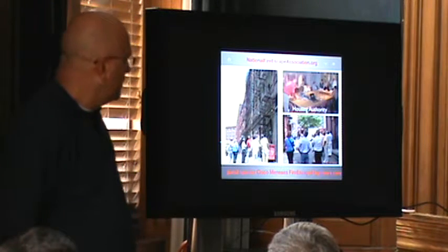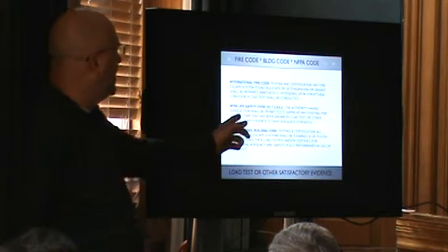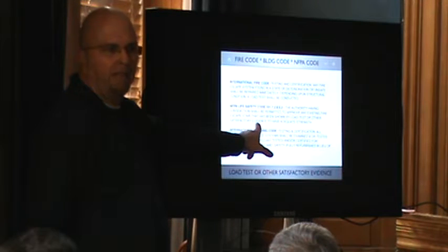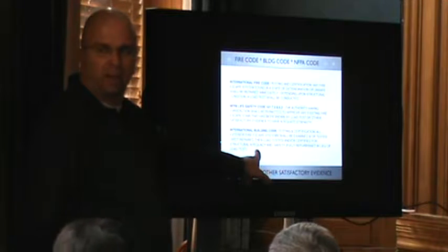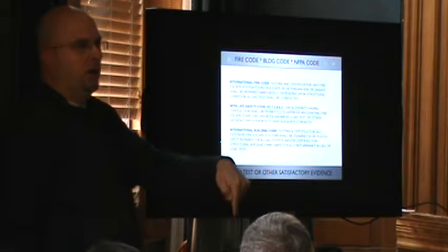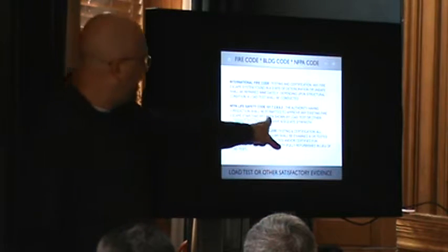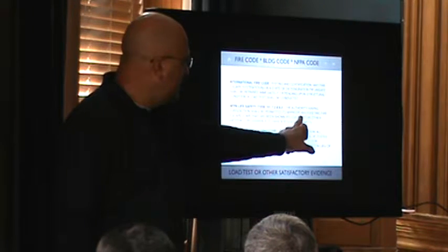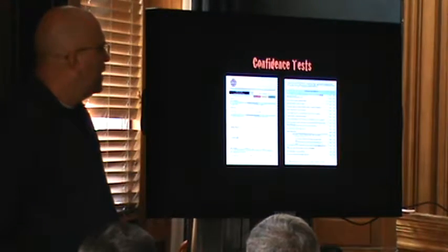Fire prevention training as well. So again, all these codes. The one thing that really helped us out was when we finally got to train everybody, we started realizing that everybody had a base of fire code, NFPA or International Building Code, and they all said the same thing. We just explained it in these classes: everybody involved in keeping a building safe is basically saying the same thing. The authority having jurisdiction shall accept a load test or other evidence of strength. And the load test was one of the key pieces. It basically made everybody start not using the opinion letters anymore.